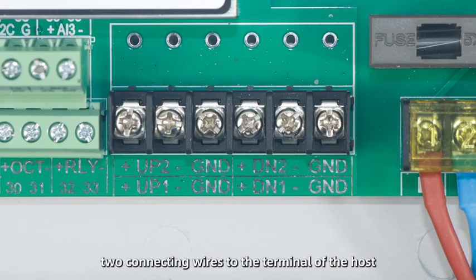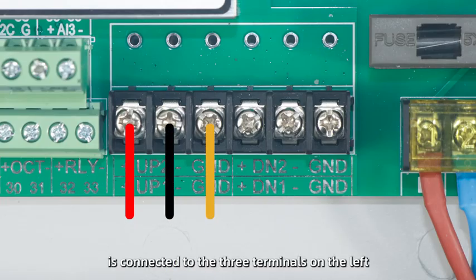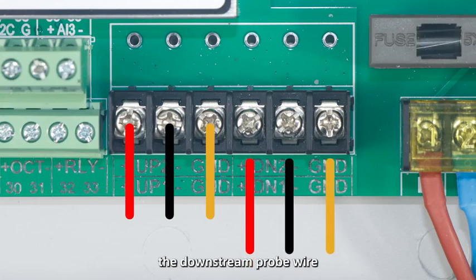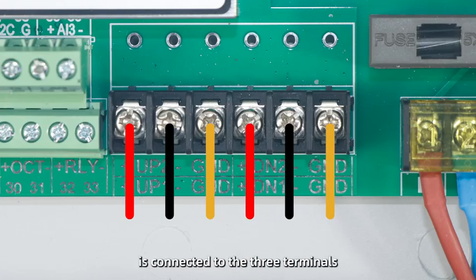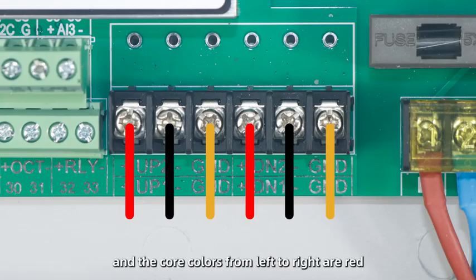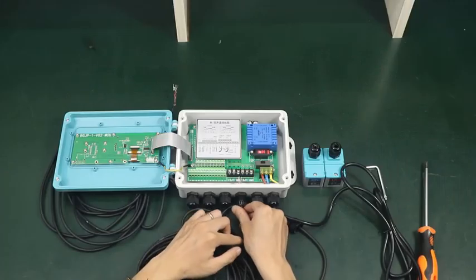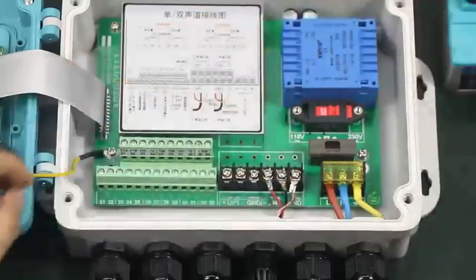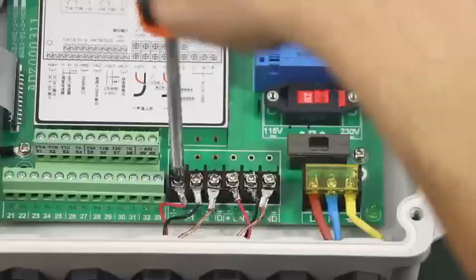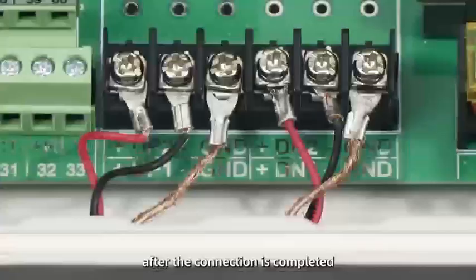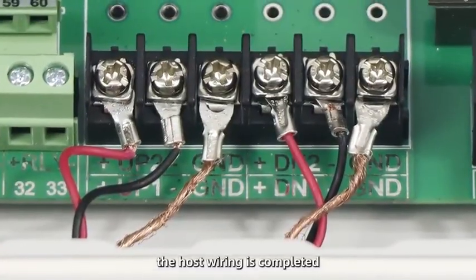First, connect 2 connecting wires to the terminal of the host. The upstream probe wire is connected to the 3 terminals on the left, and the core colors from left to right are red, black, and copper respectively. The downstream probe wire is connected to the 3 terminals on the right, and the core colors from left to right are red, black, and copper respectively. After the connection is completed, the host wiring is completed.